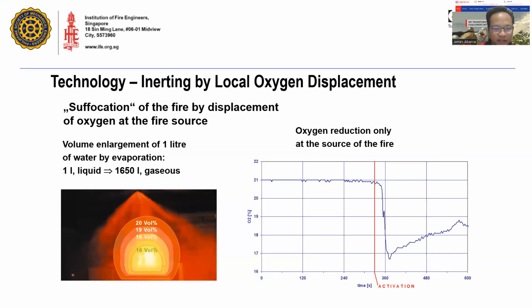Now, in terms of explaining the displacement of oxygen by inerting, that is the idea of suffocating the fire by displacing oxygen at the fire source. For 1 liter of liquid, again, our analysis is on 1 liter of liquid, there are 1,600 liters of gas being emitted. If you look at the figure on your left, you can see the percent volume of water being enlarged as it is converted into its gaseous state. It's getting higher and higher.